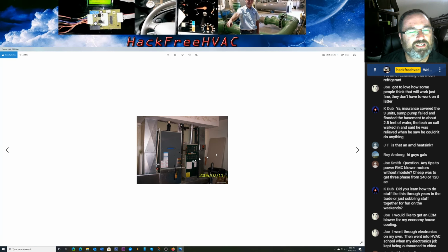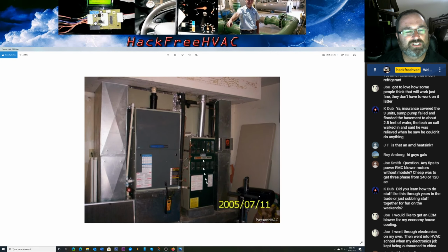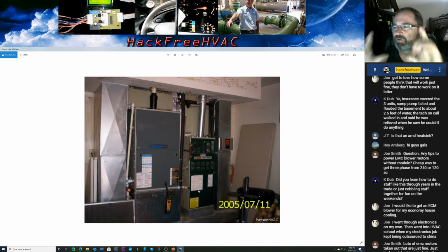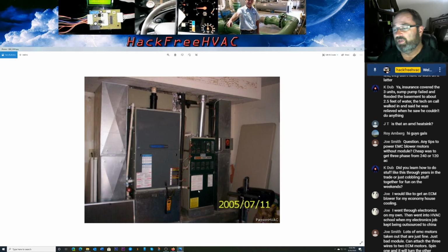All right, another picture of it here. And what happened here is this hacker company, DSC, they would go and slap stuff in without caring. So they took out—this is the original furnace here that went to that variable speed, and they had the old square module on it. This ECM motor didn't just have steps, it truly ramped up from just a crawl up to 100%.